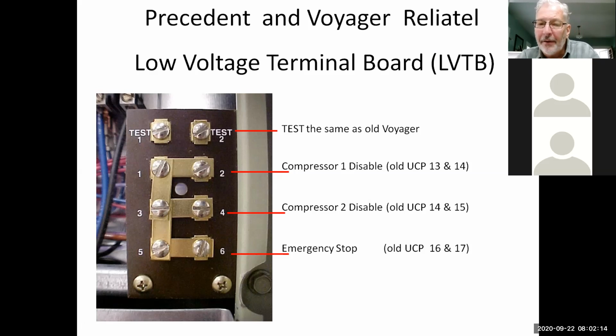Now when you get to the end of the test sequence, if you leave your jumper on there, the board's just going to ignore it and go back to normal operation. Now, if you turn the unit off at any given point during the test and turn the unit back on, it's going to ignore the jumper. If it sees a jumper on startup, it just ignores it and goes to normal operation.